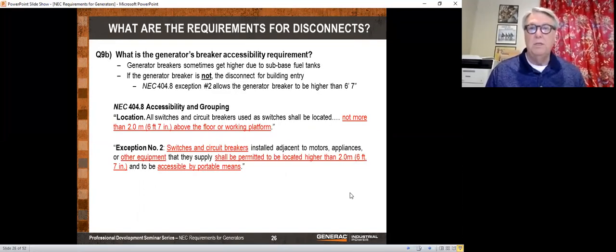B, what is the generator breaker's accessibility requirement? Well, NEC 404.8 says all switches and circuit breakers used as switches shall be located not more than 6 foot 7 inches above a floor or working platform. Obviously, the intent of this is if you have a circuit breaker, an average sized person has to be able to reach it so he can turn it off. And they decided that 6 foot 7 inches would be that level.